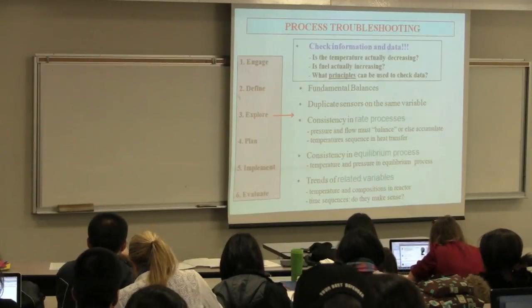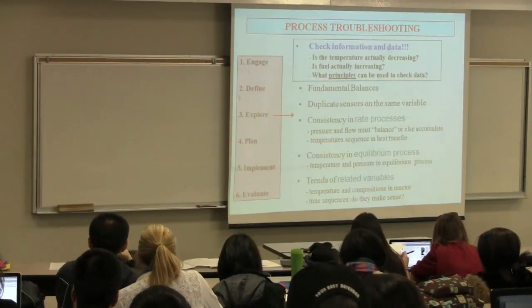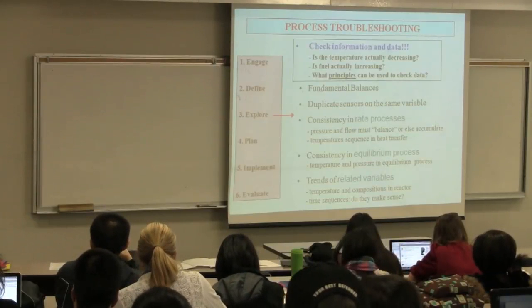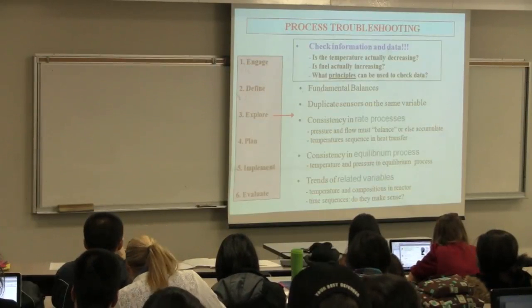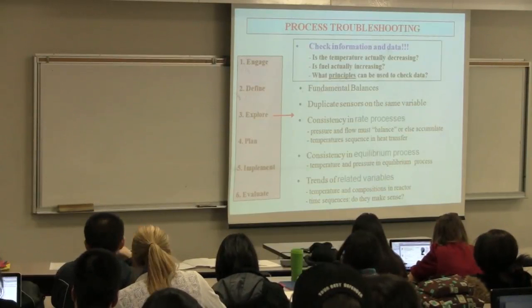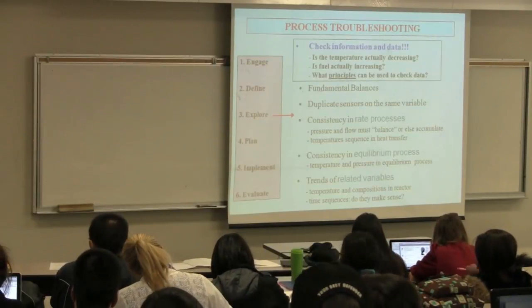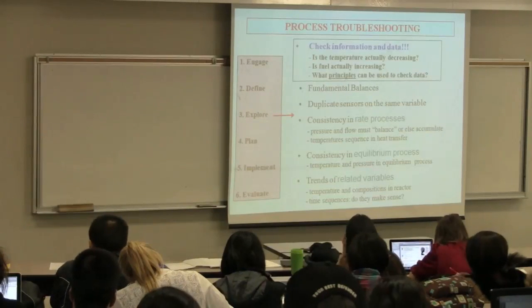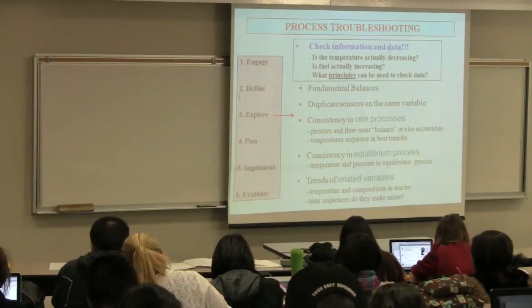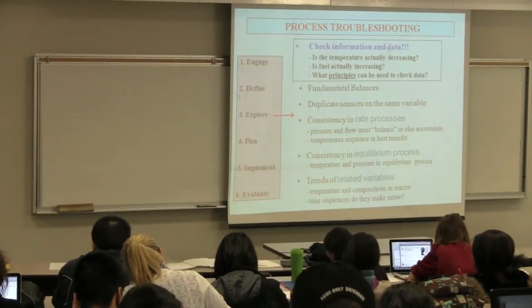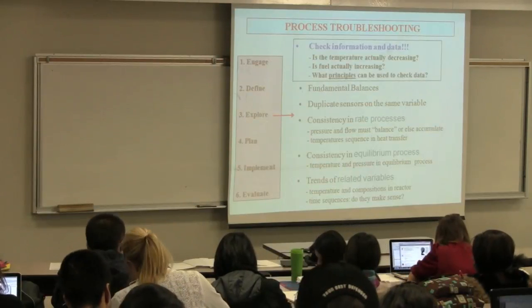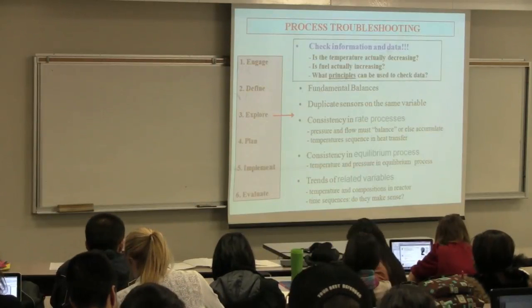We've got to be like Sherlock Holmes here. This is all that troubleshooting is. We're trying to work out who did it, what happened. So if you see that, what could you say? Faulty temperature sensor. There is a leak in my heat exchanger. Maybe I'm measuring the temperature at the wrong place. Something's gone wrong. I've got evidence that this is likely where the issue might be.